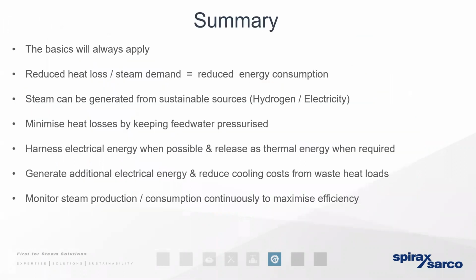So I just want to summarize very quickly what we've gone through. First of all, the basics are always going to apply. We still need to remember the principles of good working practice when it comes to generating and distributing steam. That's where we're going to get a significant payback with very little cost or effort. And we also know that if we reduce the demand for steam at the process, that's going to have a significant benefit. If we can reduce the heat loss by increasing the grade of insulation, for example, then we're going to have a significant benefit.